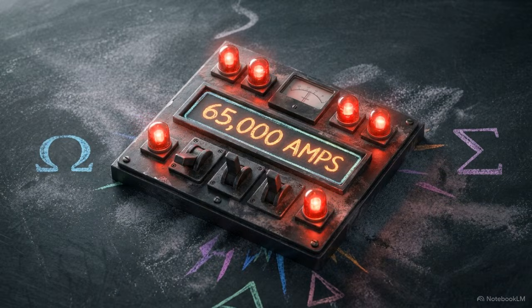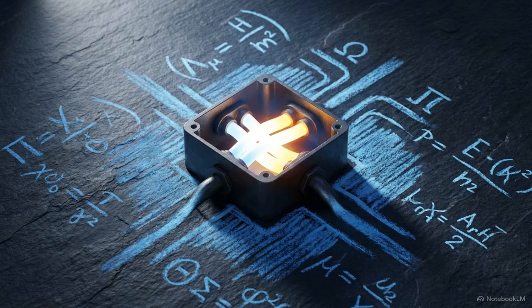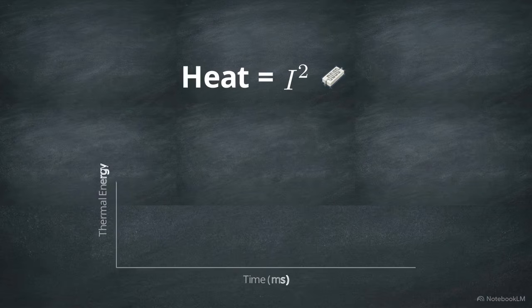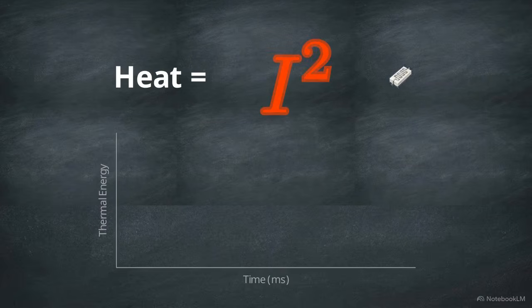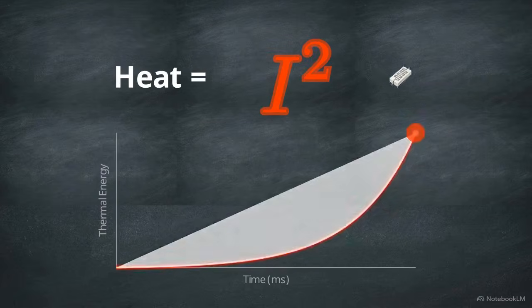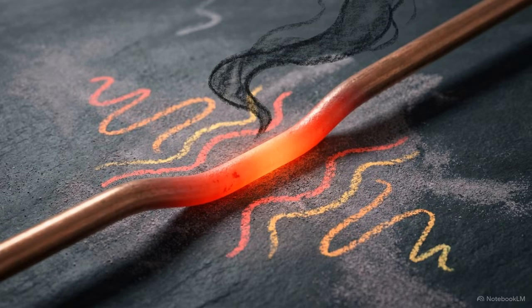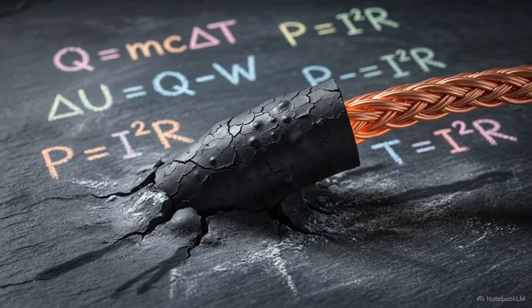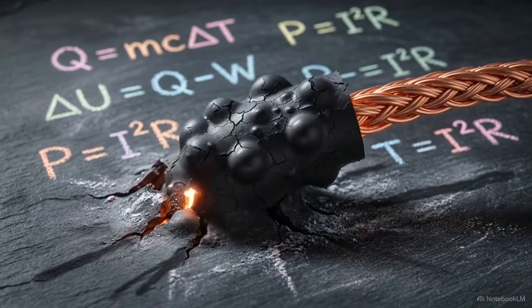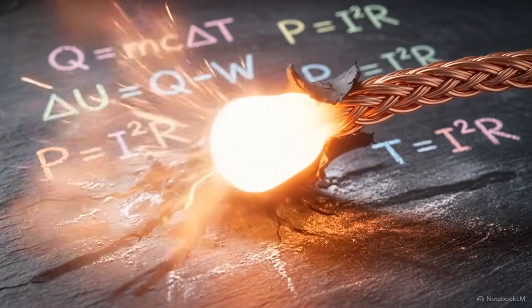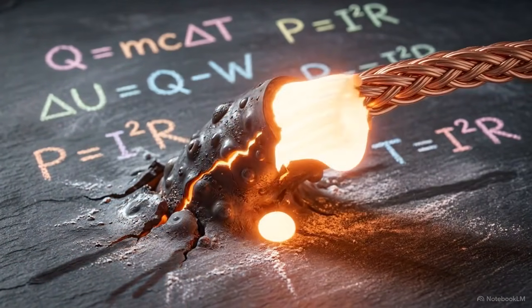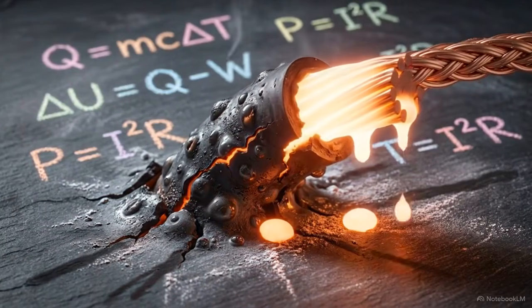The current is still surging at unimaginably high levels, and the primary danger now pivots from mechanical stress directly into severe thermal overload. According to the principles of Joule heating, the thermal energy generated is proportional to the square of the fault current. The copper wiring carrying this load essentially becomes an industrial-scaled toaster coil. The internal temperature of the system's conductors skyrockets. Within a fraction of a second, the heat surpasses the melting points of both aluminum and copper.